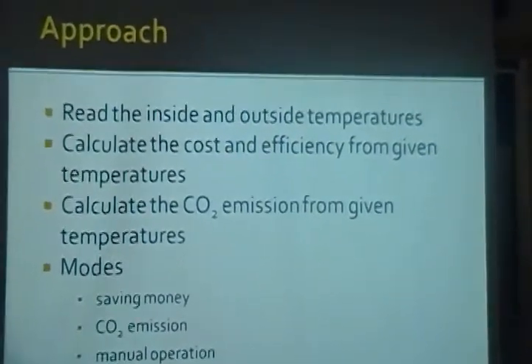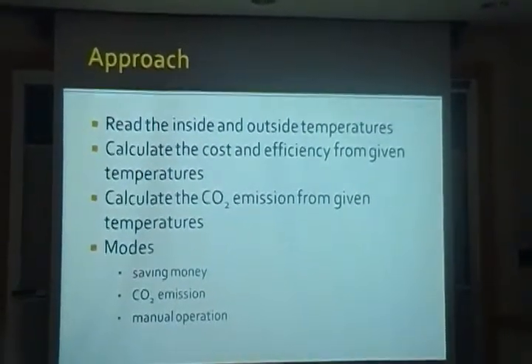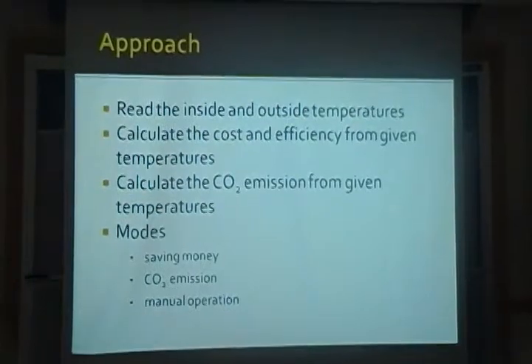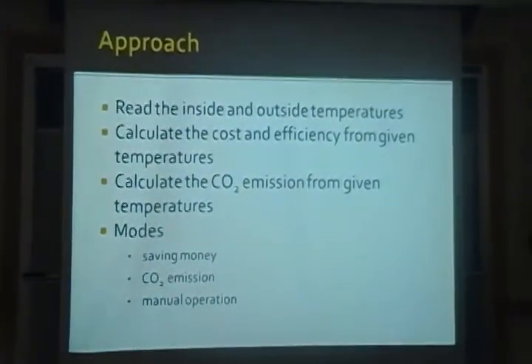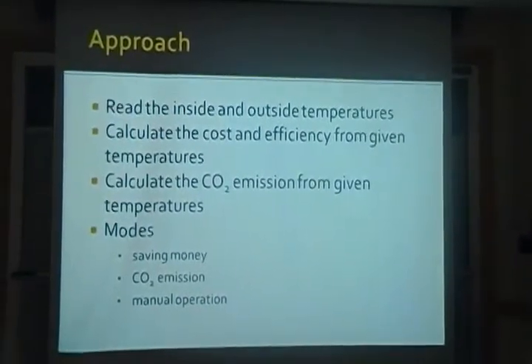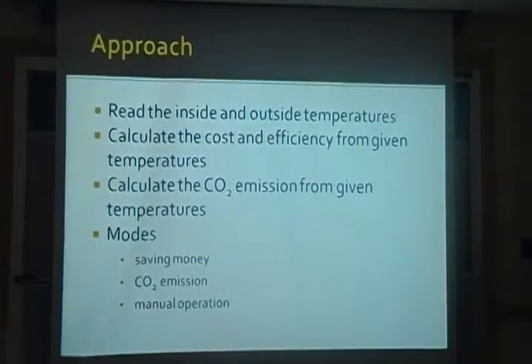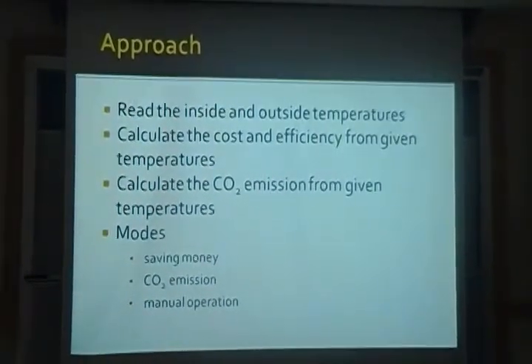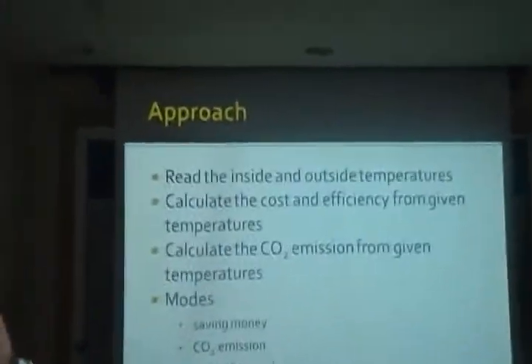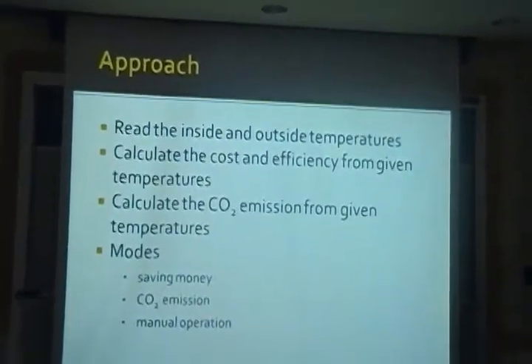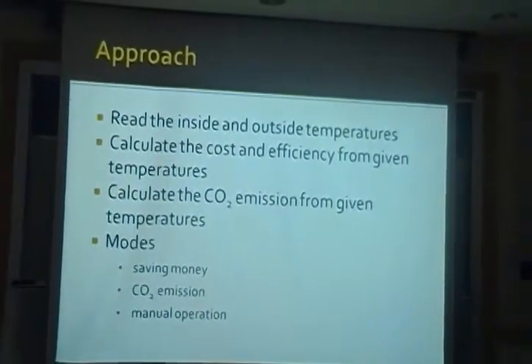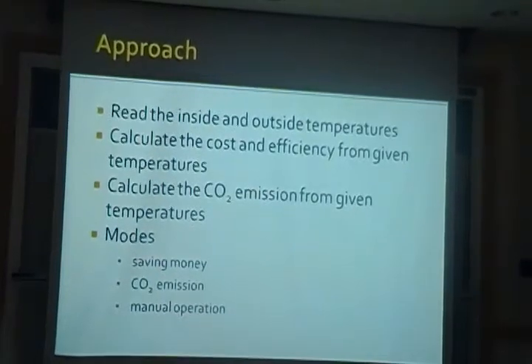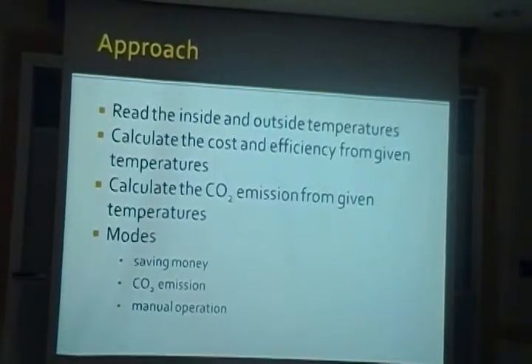The system uses two temperature inputs — one for inside and one for outside — and calculates the cost, efficiency, and carbon dioxide emission from those temperatures. The system has three modes: one for saving money, one for minimizing carbon dioxide emission, and a third for manual operation. In money-saving mode, the system calculates the cost of each heating system and switches to the less expensive one. In CO2 mode, it calculates emissions and switches to the lower-emitting system. In manual mode, the user can directly choose the heat pump or oil furnace.